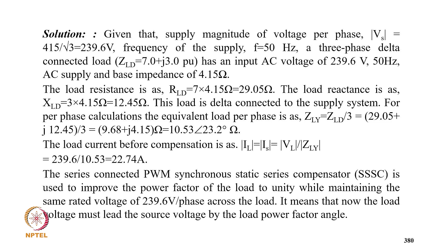It means that now the load voltage must lead the source voltage by the load power factor angle. So the magnitude of load current remains the same as earlier, whereas the phase angle of the load current is the same as the supply. Under the power factor correction, the SSSC injects the voltage difference between the supply and the load voltage under the compensation and extracts active power from the three-phase supply. A battery energy storage is required at the rating of the load voltage compensation, VL equal to VL at the angle theta, 23.2.